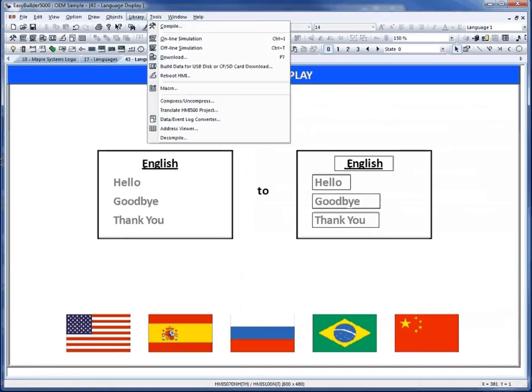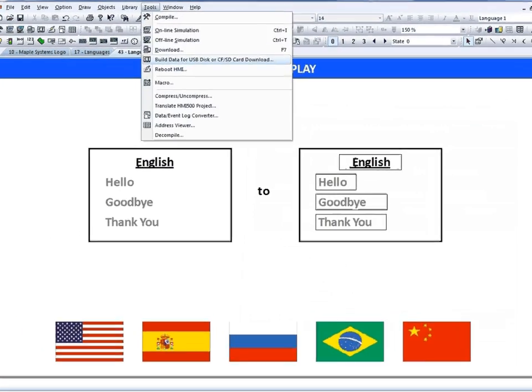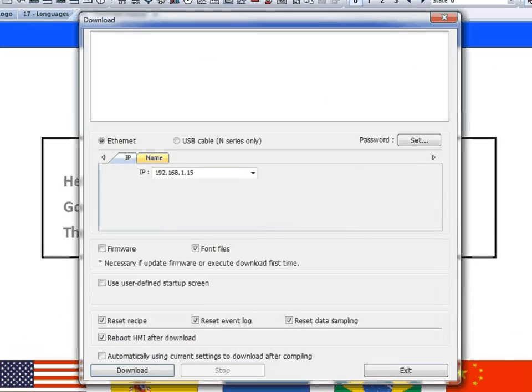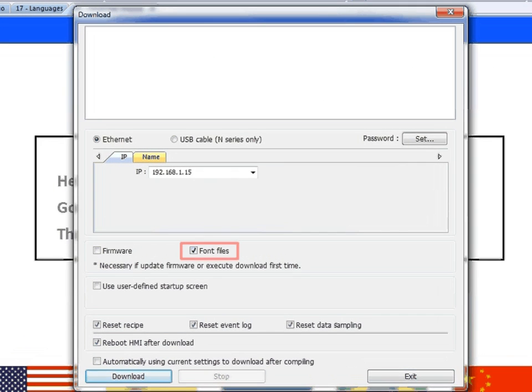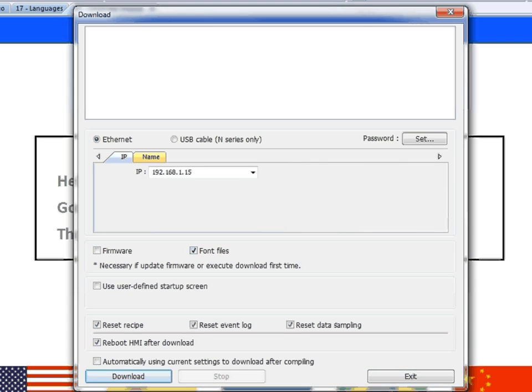When you go to download the project into your HMI, make sure that the Font Files checkbox is checked. Otherwise, you may not get certain languages to display depending on the default fonts.